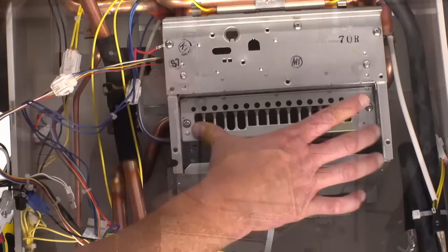Y'all got it? Okay, cool. All right. Then let's go ahead and get the burner out. We're going to do the burner next. Now, you see these two screws right here and here. We're not going to have to take those off when we're taking out the burner. That's an air damper that helps us get the right amount of air for our mixture. Okay, so we've got two screws on the bottom, on the back side of the unit. It's all the way in the burner chamber at the bottom.